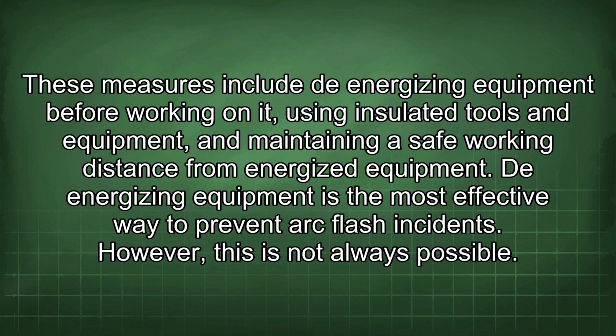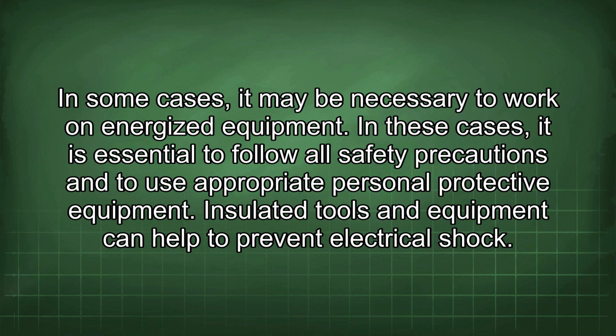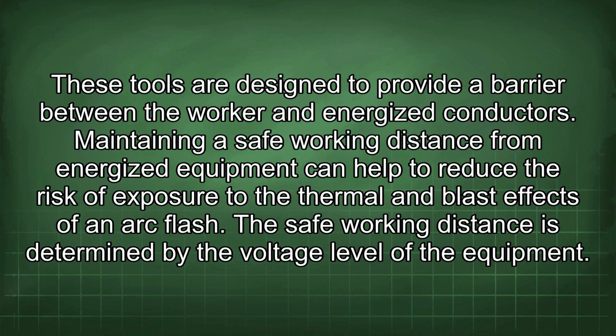De-energizing equipment is the most effective way to prevent arc flash incidents. However, this is not always possible. In some cases, it may be necessary to work on energized equipment. In these cases, it is essential to follow all safety precautions and to use appropriate personal protective equipment. Insulated tools and equipment can help to prevent electrical shock. These tools are designed to provide a barrier between the worker and energized conductors. Maintaining a safe working distance from energized equipment can help to reduce the risk of exposure to the thermal and blast effects of an arc flash. The safe working distance is determined by the voltage level of the equipment.